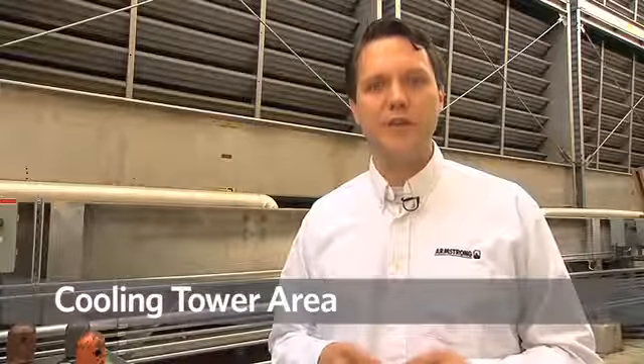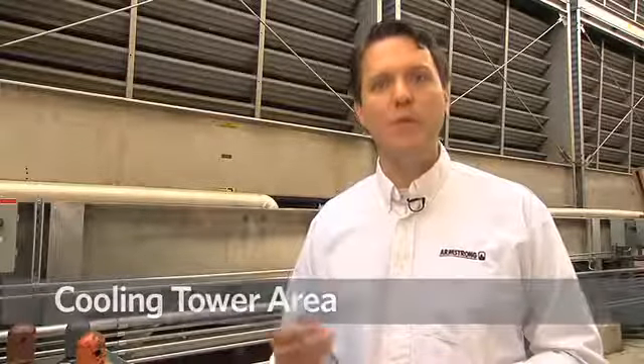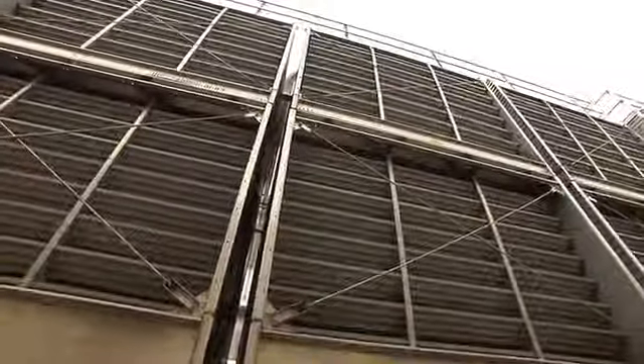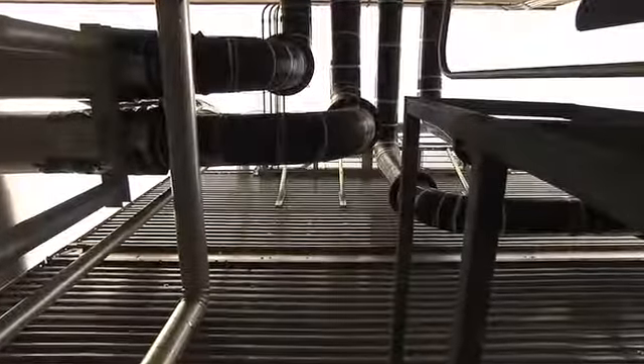towers outside. Here we are outside the cooling tower area at the hospital, where behind me we have the 4 new cooling tower cells that were installed in 2012. Each tower is sized for 1,000 tons each and was supplied with a variable frequency drive on the tower fan. Additionally, they were selected for variable water flow so that the Armstrong IPC controller can maximize the part load efficiency of the towers. The previous towers were old wooden fill towers that were in dire need of replacement, so that now, after the installation, the hospital can take advantage of the efficiency gains from the IPC control system.